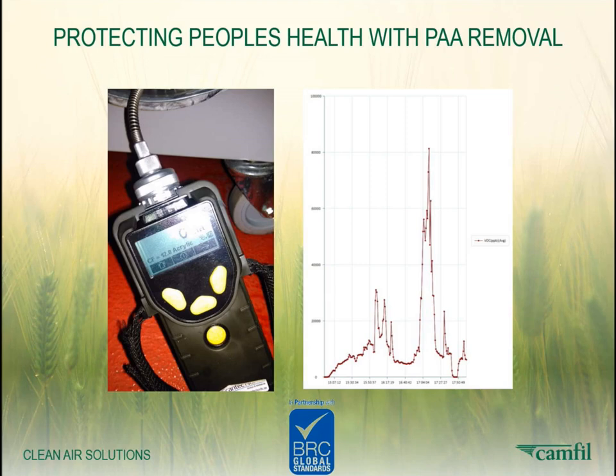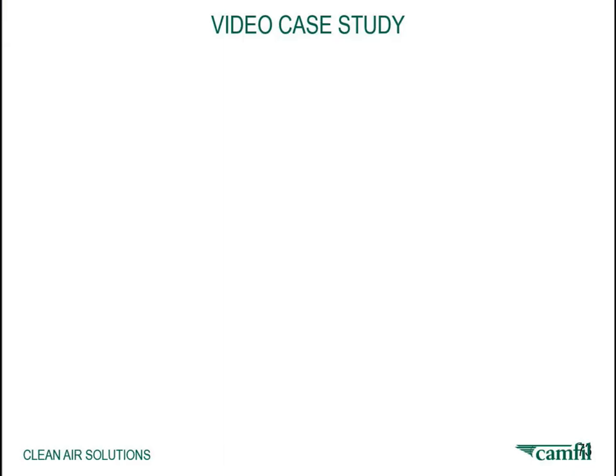In the picture to the left, you see the zero reading at the supply air of the unit. In the diagram, you see the real-time graph of the measurements. Initially, PAA levels were between 10 to 27 ppm in the first hour of monitoring before the trial began. Once air cleaning was started, the levels dropped by 75% within 25 minutes after switching on the unit. There are several identified safe levels and guidelines in Europe and by the EPA in the US for those substances. Please take 3 minutes to watch our customer explain this project in more detail.